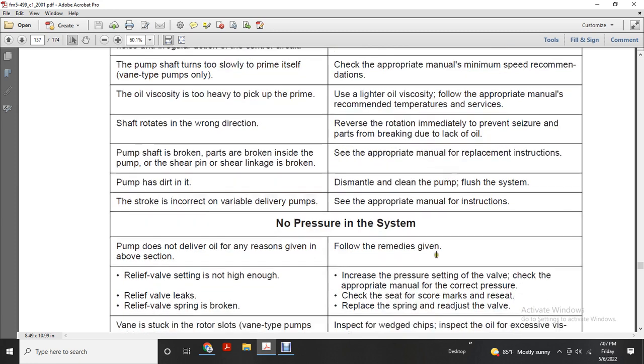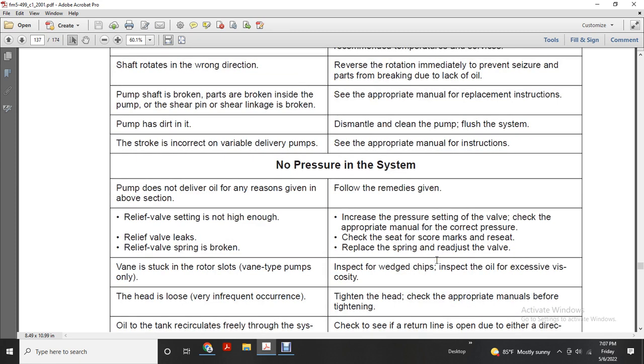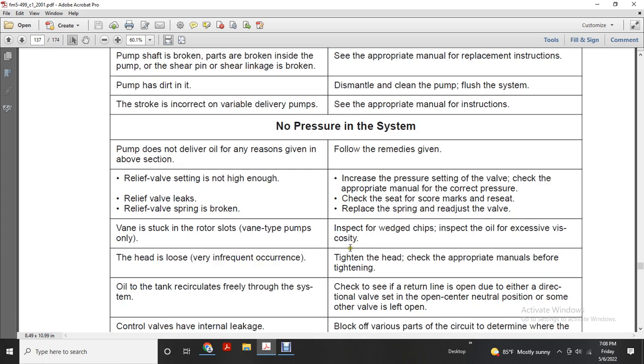See the appropriate manual for instructions. No pressure in the system: piston pumps did not deliver any oil for any reason given in the above section. Follow the remedies given. Relief valve setting is not high enough, relief valve leaks, or relief valve spring is broken. Increase the pressure setting; check the appropriate manual for the correct pressure. Check the seat for score marks and reseat. Replace the spring and readjust the valve.